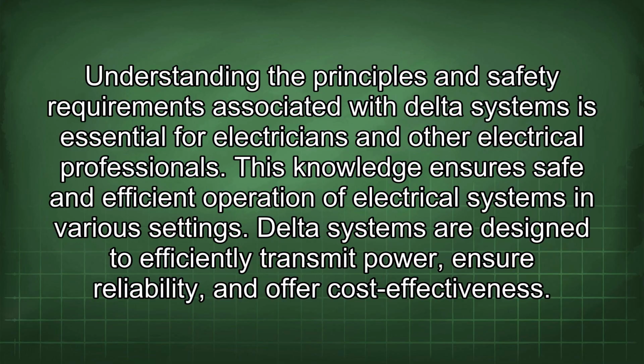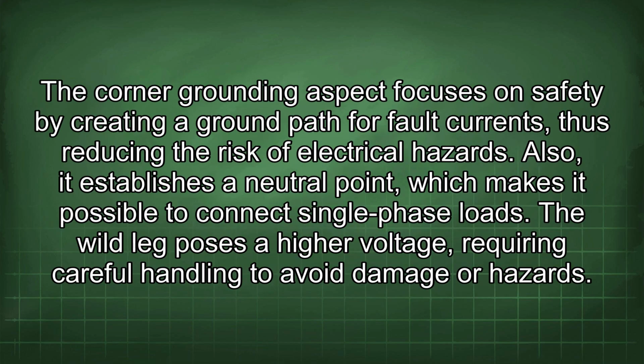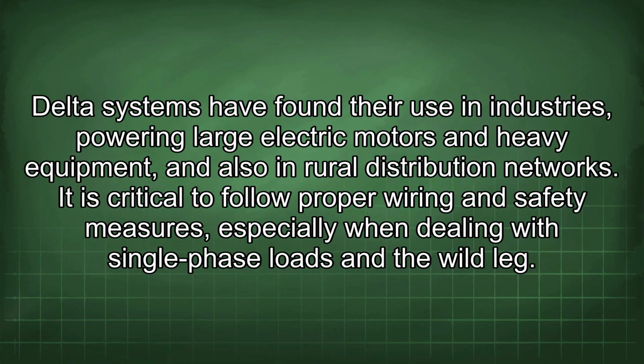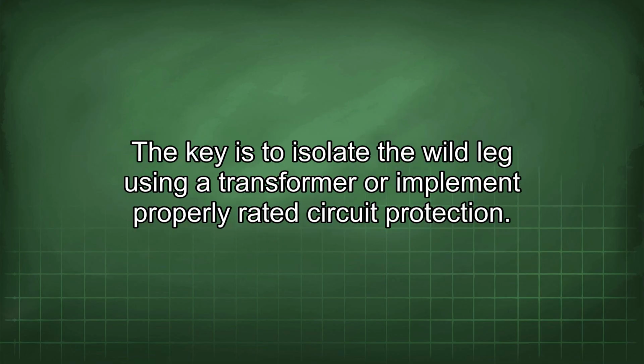Delta systems are designed to efficiently transmit power, ensure reliability, and offer cost-effectiveness. The corner grounding aspect focuses on safety by creating a ground path for fault currents, thus reducing the risk of electrical hazards. Also, it establishes a neutral point, which makes it possible to connect single-phase loads. The wild leg poses a higher voltage, requiring careful handling to avoid damage or hazards. Delta systems have found their use in industries, powering large electric motors and heavy equipment, and also in rural distribution networks. It is critical to follow proper wiring and safety measures, especially when dealing with single-phase loads and the wild leg. The key is to isolate the wild leg using a transformer or implement properly rated circuit protection.